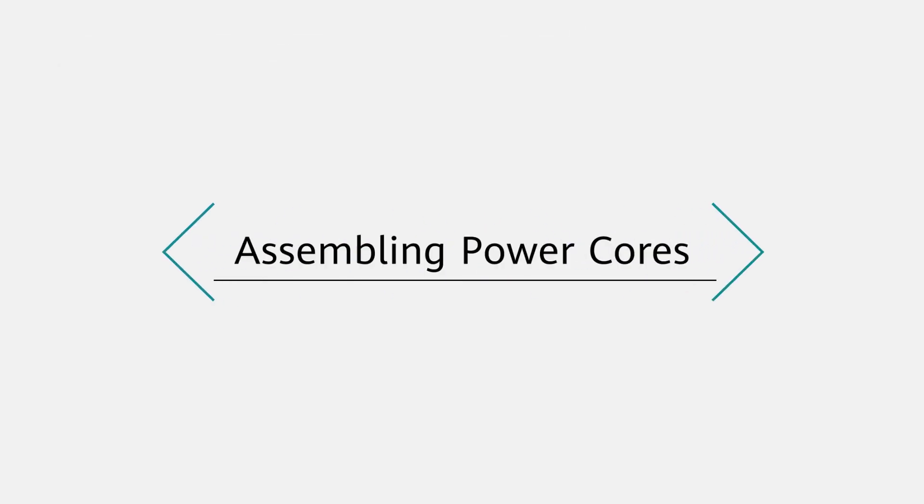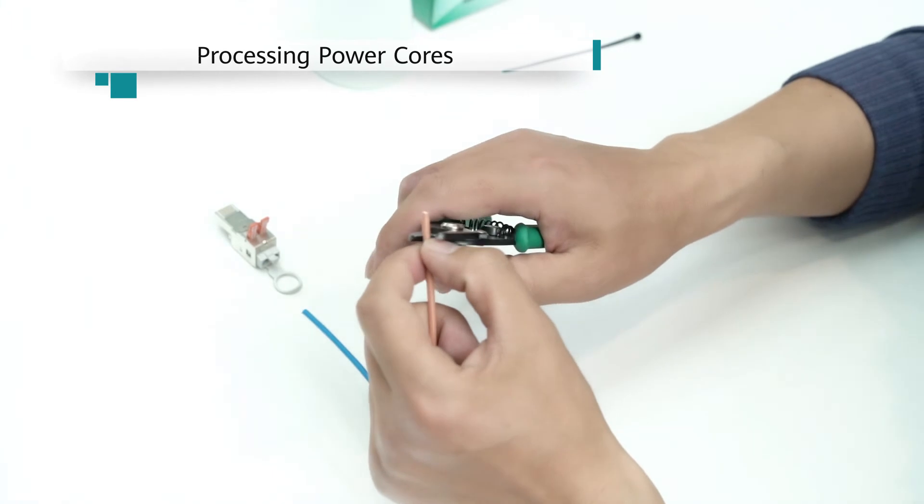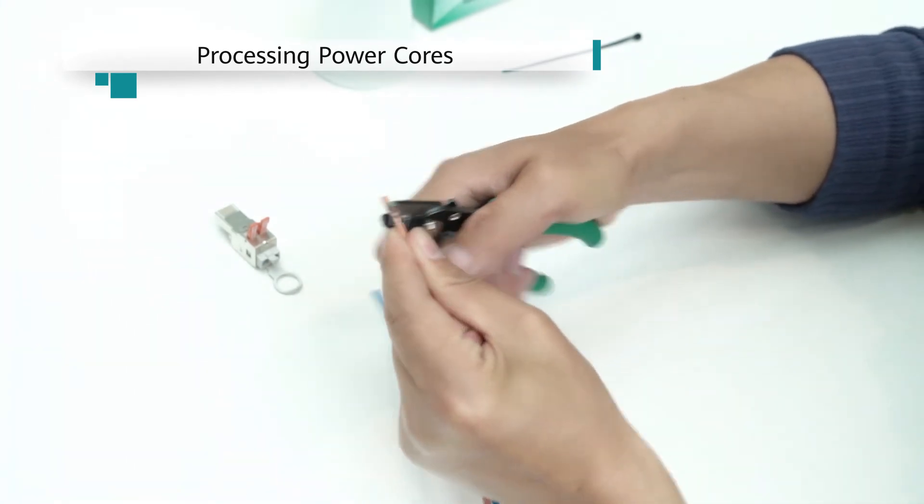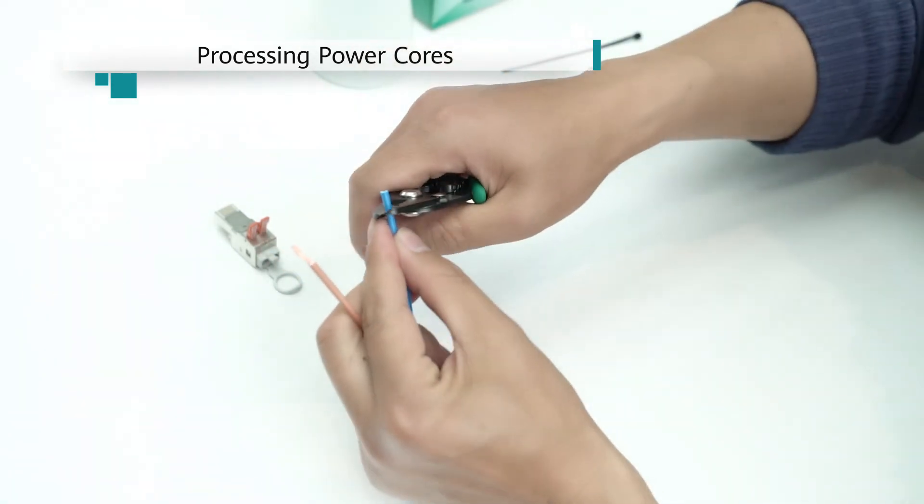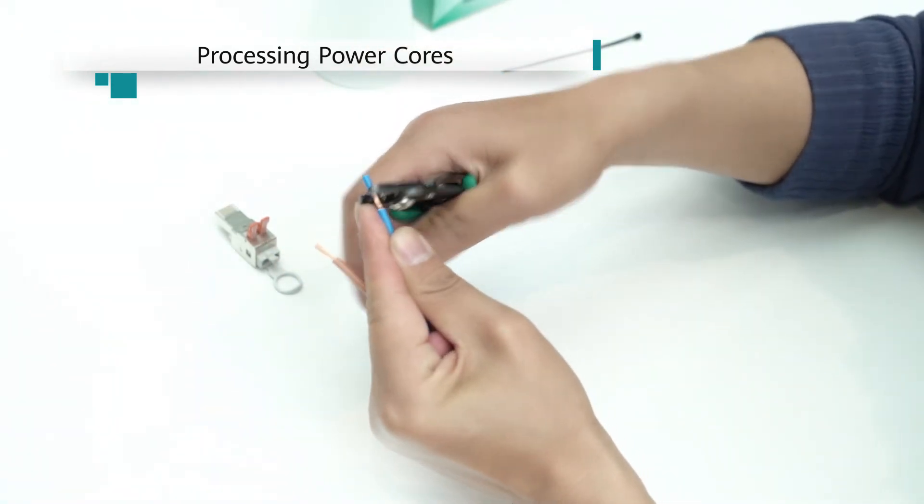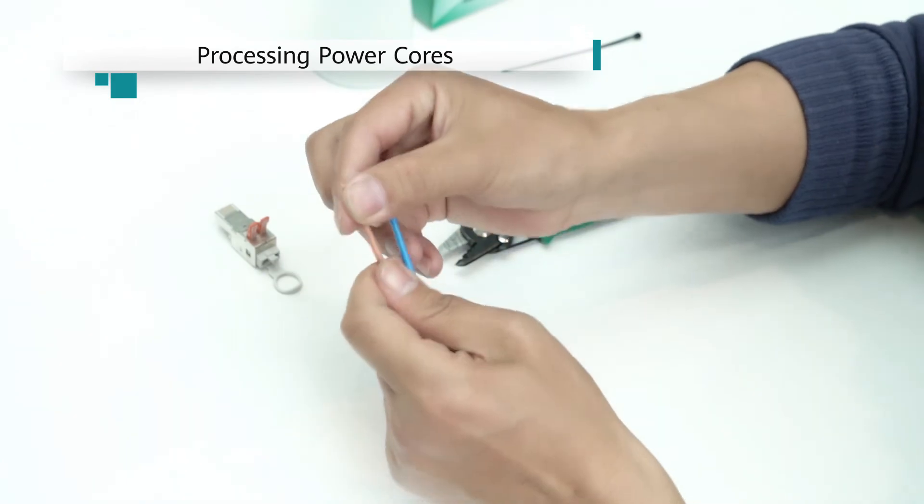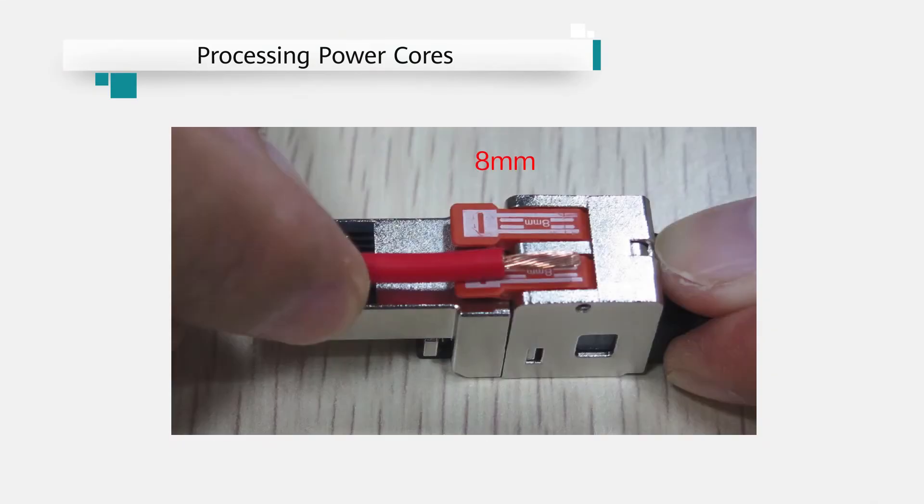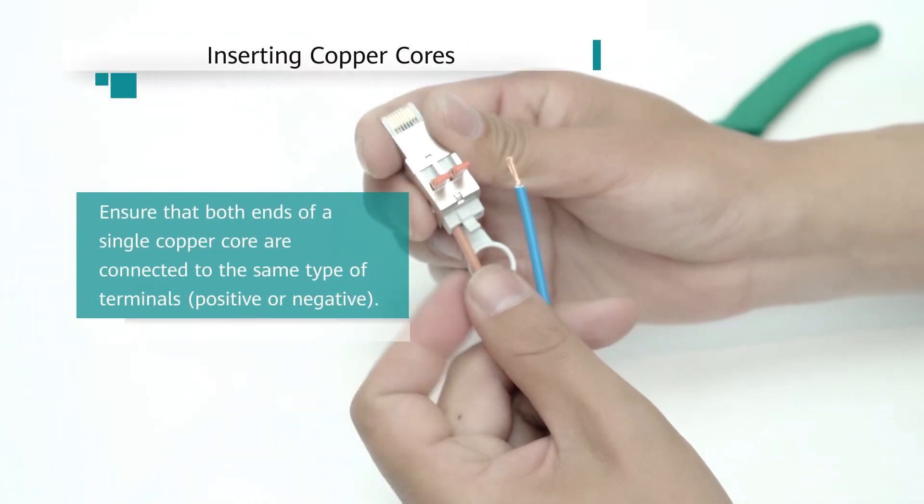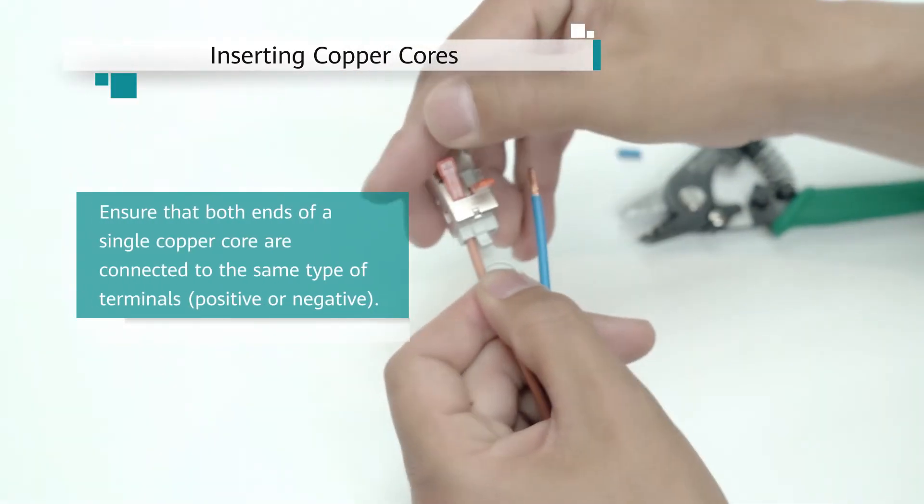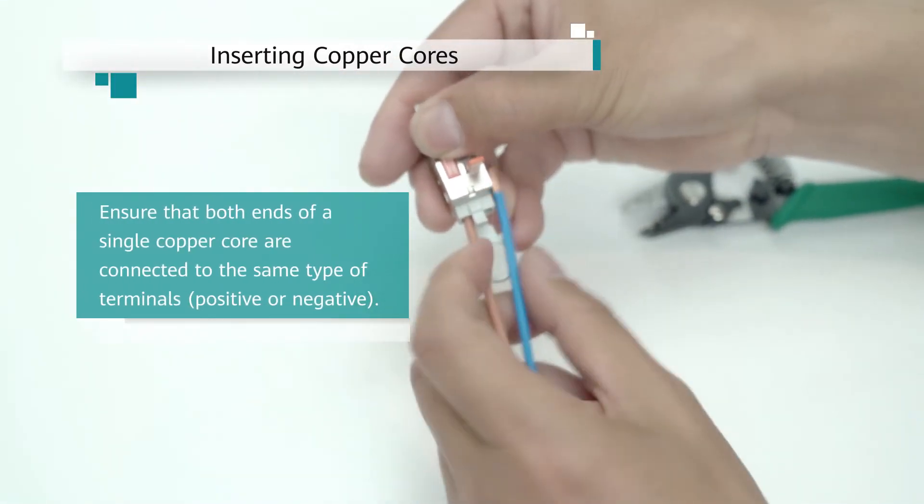Assembling power cores. Peel 8 mm of insulation coating off each power core. Fully raise the levers of a power connector as shown in the video. Insert the copper cores all the way into the cable inlets. Ensure that no copper conductors are bent or exposed.